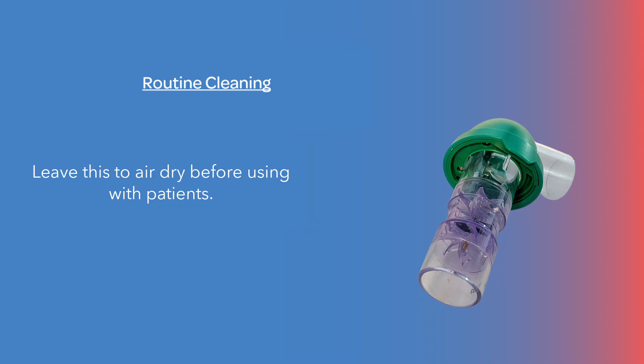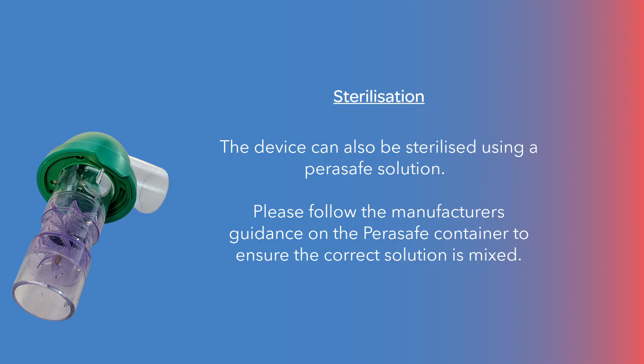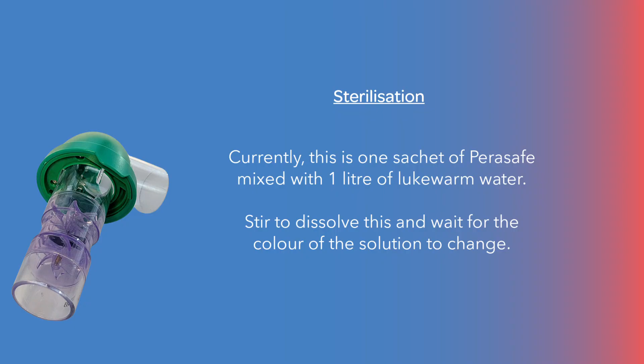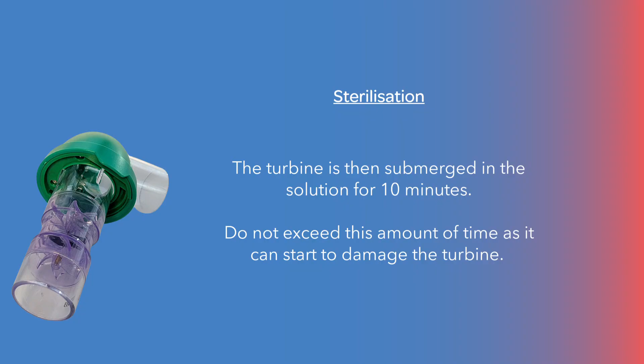Sterilization. The device can also be sterilized using a Perasafe solution. Please follow the manufacturer's guidance on the Perasafe container to ensure the correct solution is mixed. Currently, this is 1 sachet of Perasafe mixed with 1 liter of lukewarm water. Stir to dissolve this and wait for the color of the solution to change. The turbine is then submerged in the solution for 10 minutes. Do not exceed this amount of time as it can start to damage the turbine.